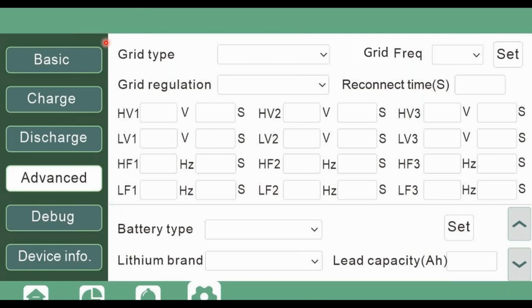Moving on into the advanced section, here you would set the grid type. Which grid type: 120/240, 120/208. Here you would set the frequency. We can do 60 hertz and 50 hertz as well. And then here you would set the grid regulation, right? Right now you can use US or US Rule 21, UL, IEEE, Luma, HECO. Luma for Puerto Rico, HECO for Hawaii. And it will generate the voltage readings according to those regions.